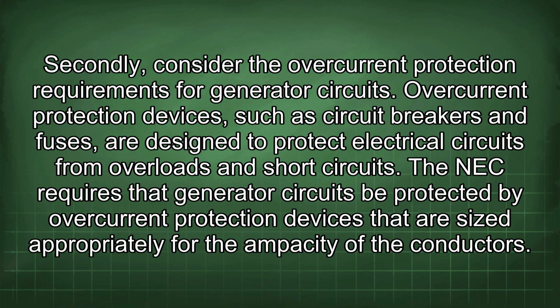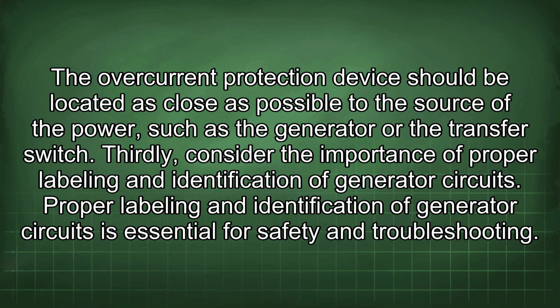The NEC requires that generator circuits be protected by overcurrent protection devices that are sized appropriately for the ampacity of the conductors. The overcurrent protection device should be located as close as possible to the source of the power, such as the generator or the transfer switch. Thirdly, consider the importance of proper labeling and identification of generator circuits. Proper labeling and identification of generator circuits is essential for safety and troubleshooting.